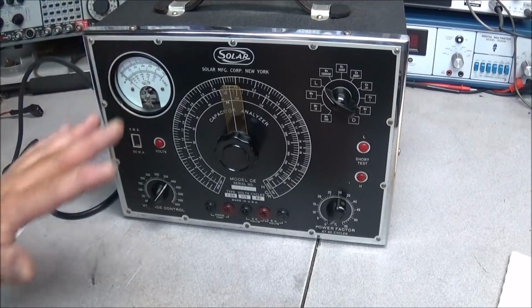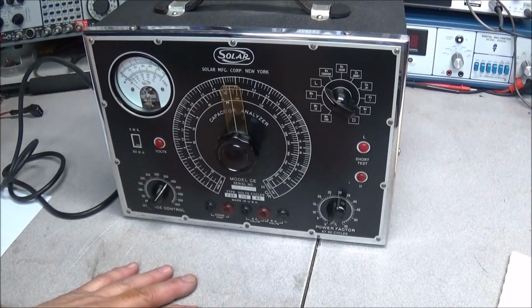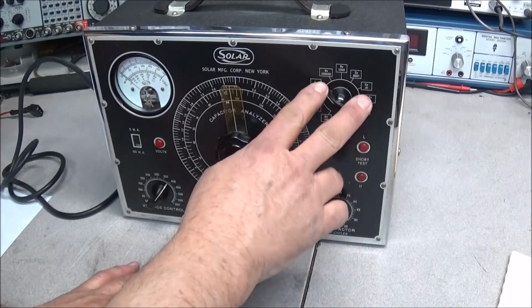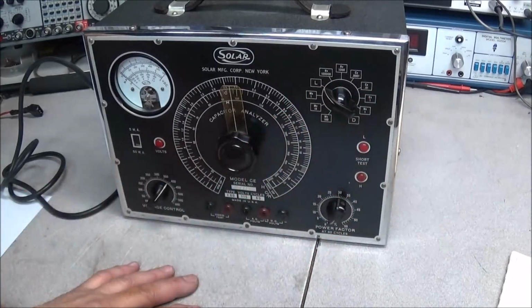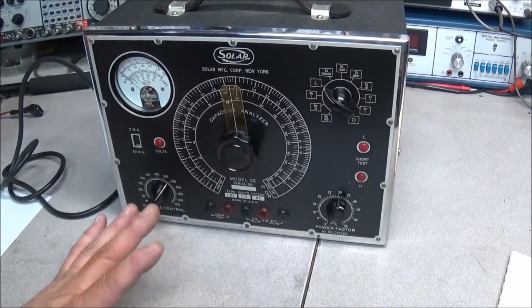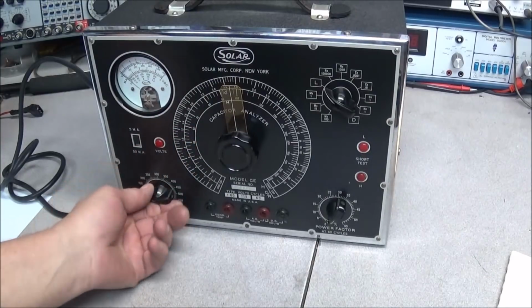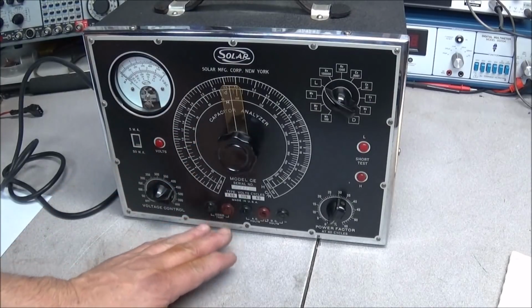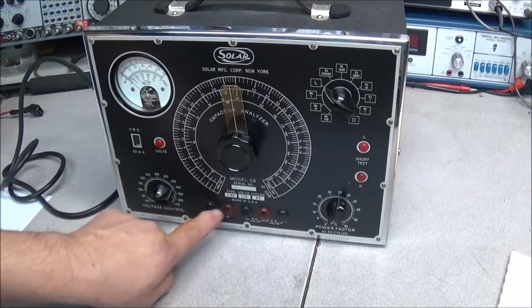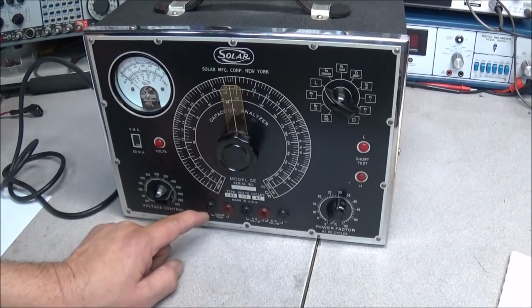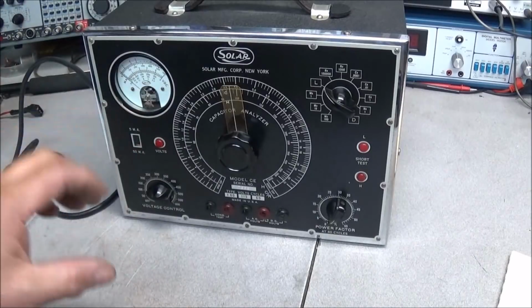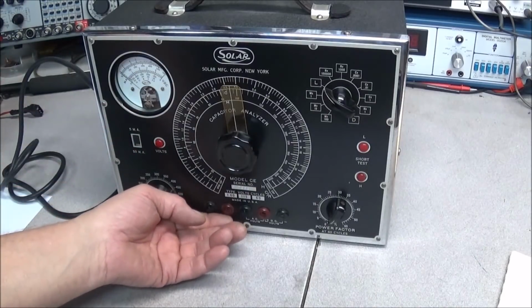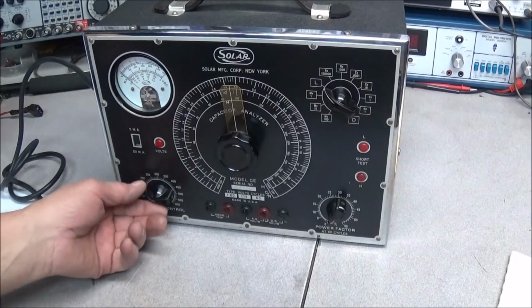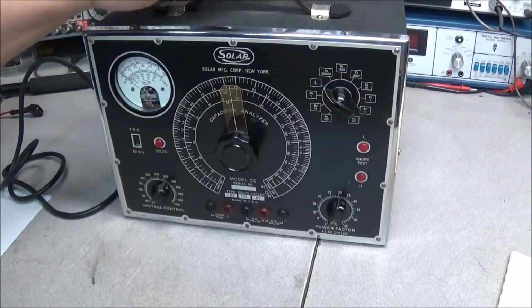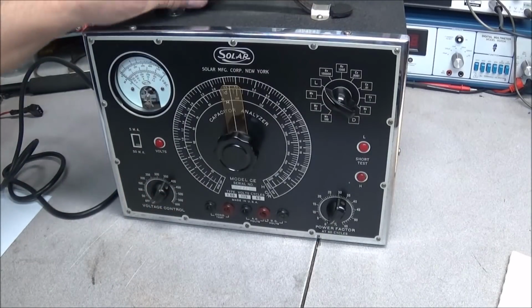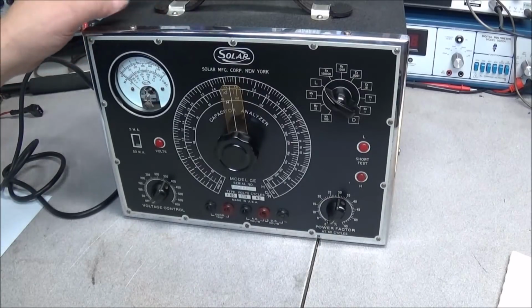Also, whenever you're using something like this and you have a capacitor, your leakage is done up here in the switch. There's no discharge on this thing, so always turn everything down when you go in, because this goes up to 600 volts on these terminals right here. So if you get one of these, be very careful, because it is dangerous. It can make for a bad day. But excellent little piece of equipment, very nice. Even the leather handle on top looks real good.